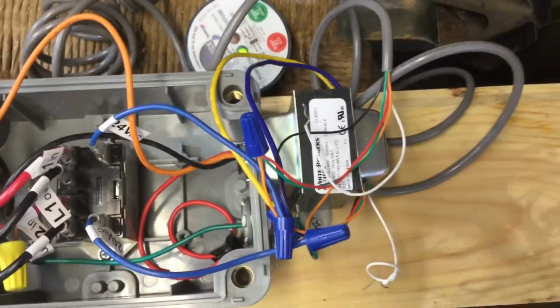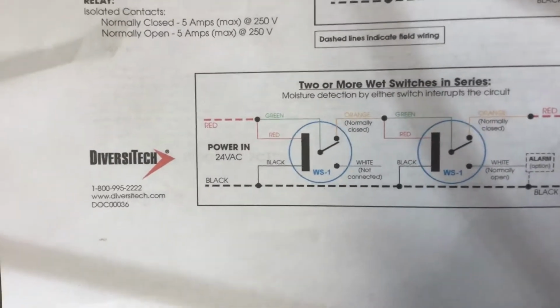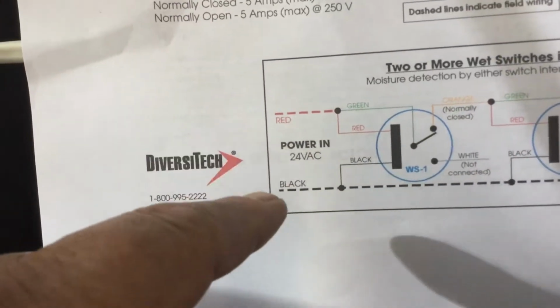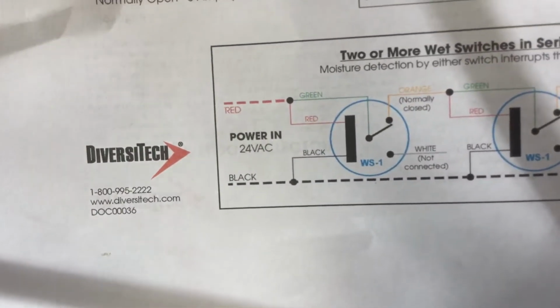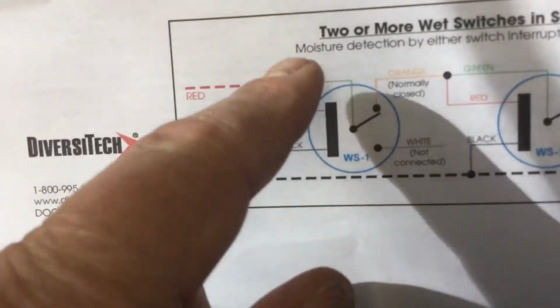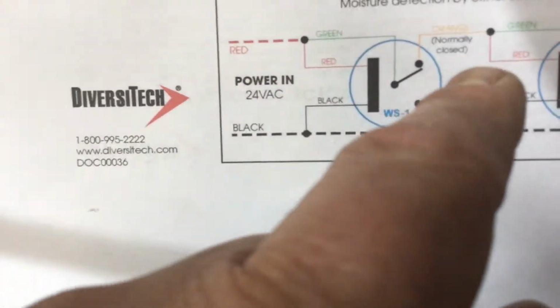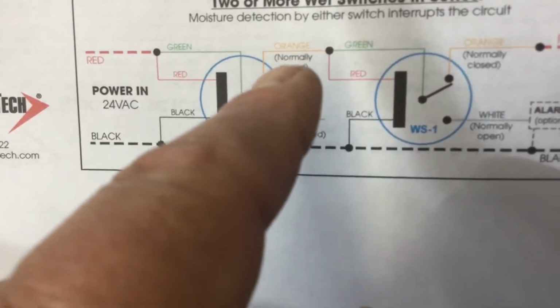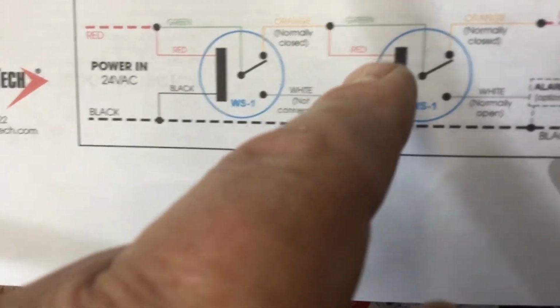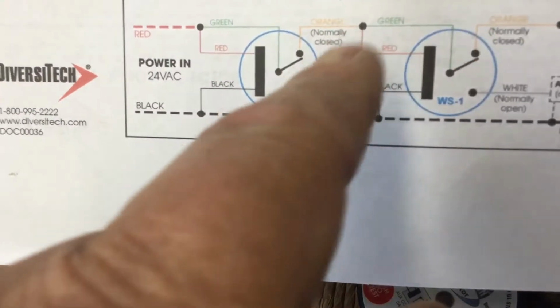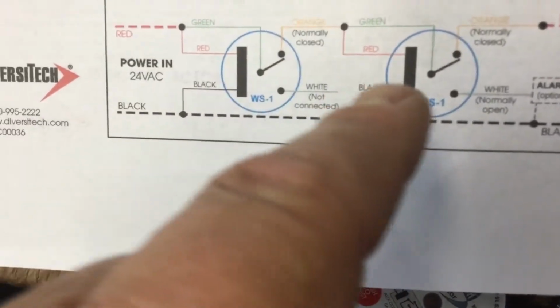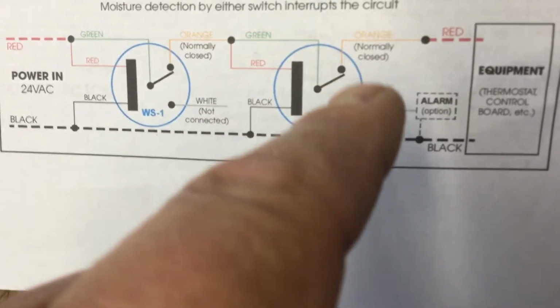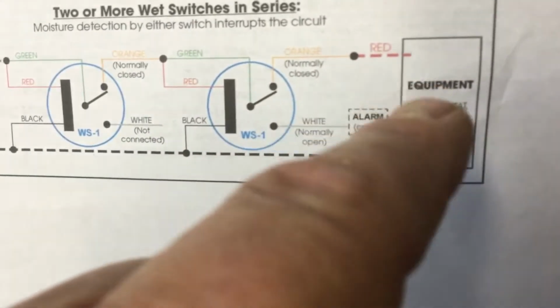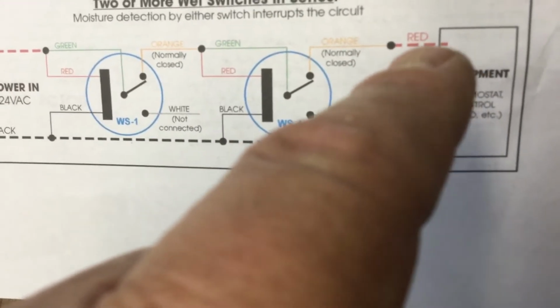So the switches, looks complicated. They have 5 wires. They actually give you a nice diagram. So the red and the black are your power lines from your transformer. They connect up to the red and green on the switch. The orange coming out of the first switch connects to the red and green of the second switch. So that is powering up your switches. That gives the switches power. And then the orange comes out of the switch and goes to, well, in my case, blue, one of the lines going in to the relay.